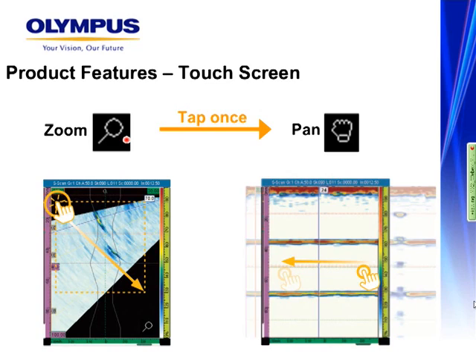While in zoom mode, with the exception of the blue data cursor on the S-scan and C-scan, all of the cursors and gates are disabled on the touchscreen. This was necessary because fat fingers would otherwise manipulate small, detailed cursors in positions where the gates, cursors, and your desired zoom area were too close together. For the zoom mode, there are two features displayed with the two icons you see here: zoom and pan. Tapping one time on the zoom button enables the pan.